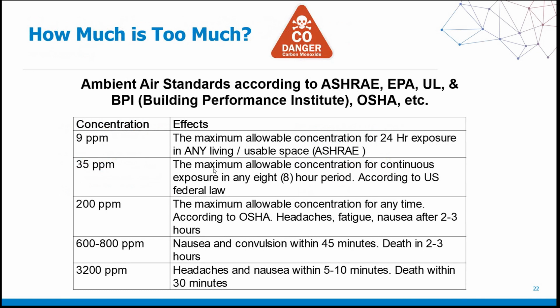When I talked about levels a second ago, here are two that I want you to really key off on. 9 ppm over a 24-hour period in any living space, and 35 ppm, maximum allowable over an 8-hour exposure. And that is technically your working day space, wherever your office is. So those two numbers, I want you to understand at the foundational level and keep in the back of your mind as you look at your analyzer and try to conceptualize the levels that you're seeing.